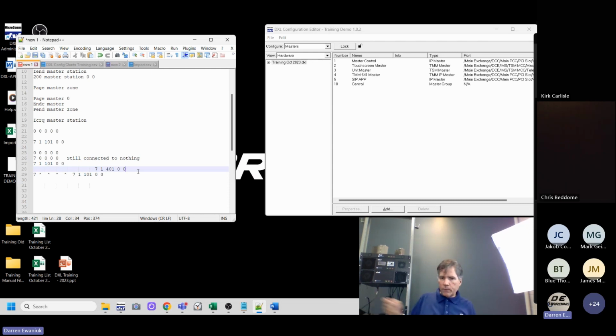So what we have in the peer-to-peer method is what's called a handshake registry. The intercom system will write the updates into your system. When your logic has processed it, you send the response back to the intercom system saying, I processed it, give me the next one. We call that a handshake. The intercom system will write the updates into your system, and if there's another update waiting, it'll wait. Once your system has processed it, it will send a handshake.